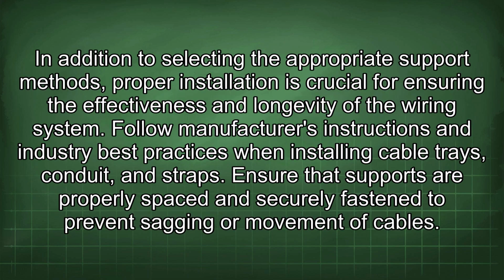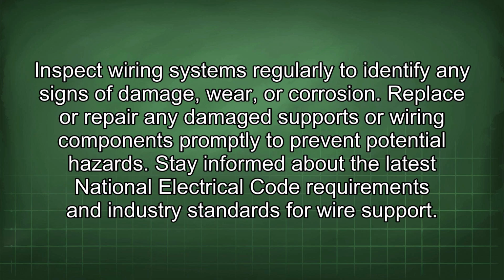In addition to selecting the appropriate support methods, proper installation is crucial for ensuring the effectiveness and longevity of the wiring system. Follow manufacturer's instructions and industry best practices when installing cable trays, conduit, and straps. Ensure that supports are properly spaced and securely fastened to prevent sagging or movement of cables. Inspect wiring systems regularly to identify any signs of damage, wear, or corrosion. Replace or repair any damaged supports or wiring components promptly to prevent potential hazards.